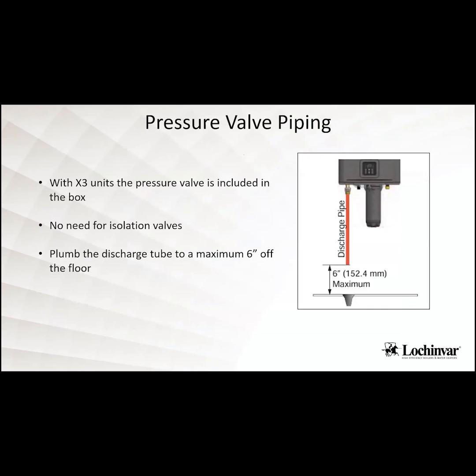All right. So that pressure valve that comes with the X3 units, there is that on the hot side coming out, there is a port there that just screws into. So again, you do not need to have the isolation valves that are there. When you run your discharge pipe off of there, we just wanted a maximum of 6 inches off the floor coming out. We don't want it to go down into a drain, down inside of a P-trap or anything like that, but the maximum off the ground is 6 inches.